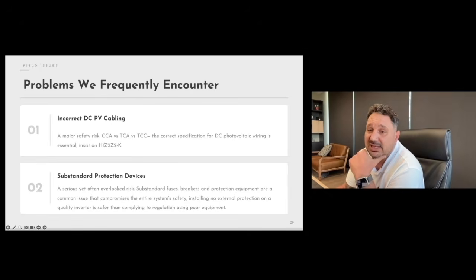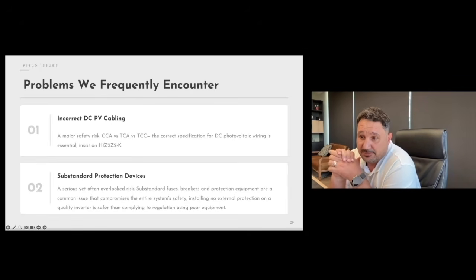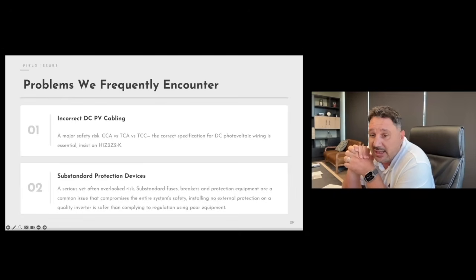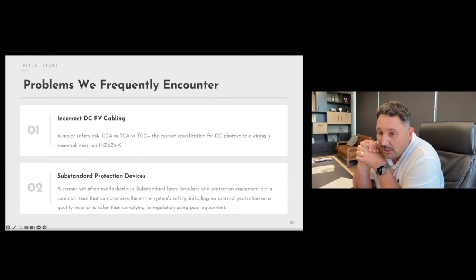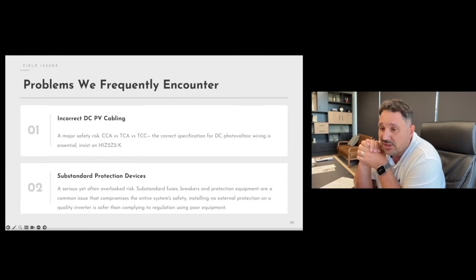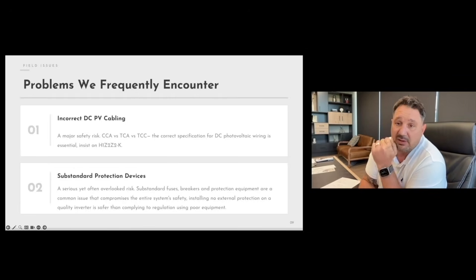Another concern is the use of substandard protection devices. This is a common issue in many installations and presents a serious yet often overlooked risk. Modern-day inverters are equipped with high-quality built-in protection that has been rigorously tested and designed to provide effective protection under real-world conditions. Unfortunately, there is a widespread misconception that additional external devices are always required. In many cases, this leads to the poor installation of low-quality or incorrectly specified equipment, which does more harm than good. Poor quality equipment may fail catastrophically under surge conditions, potentially increasing the risk of fire rather than reducing it. And that is a very, very big concern.